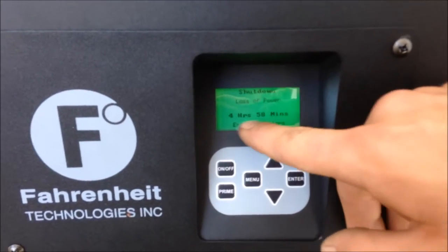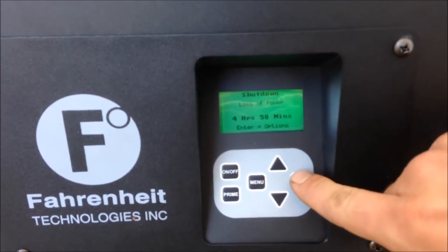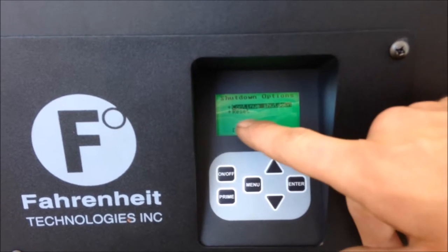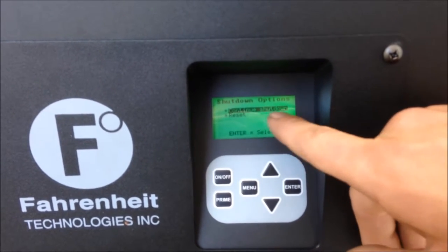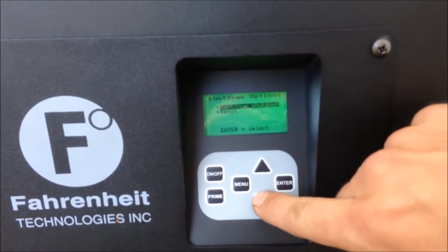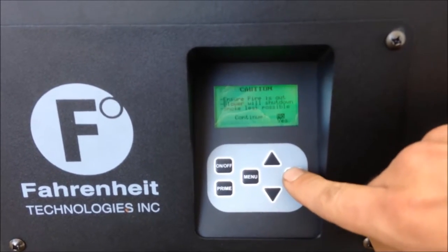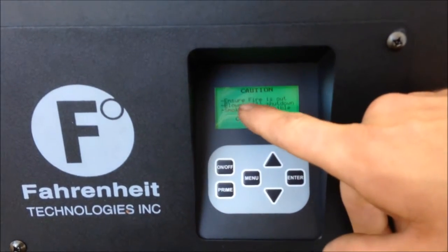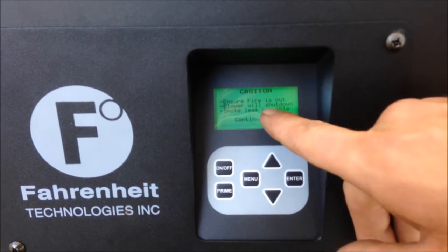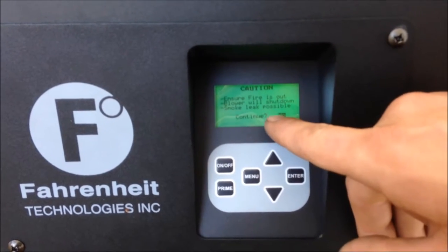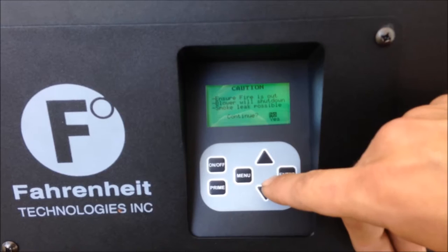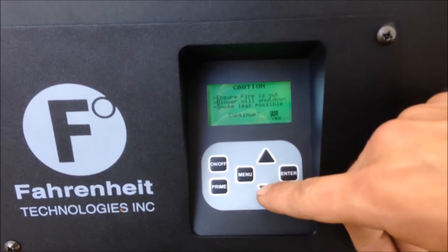Shutdown, loss of power, 4 hours and 58 minutes. Shutdown options are continue shutdown or reset. Press down to go to reset. Press enter. Caution. Ensure fire is out. Blower will shut down. Smoke leak possible. In this case, we do not have a fire present, so we can continue the shutdown.